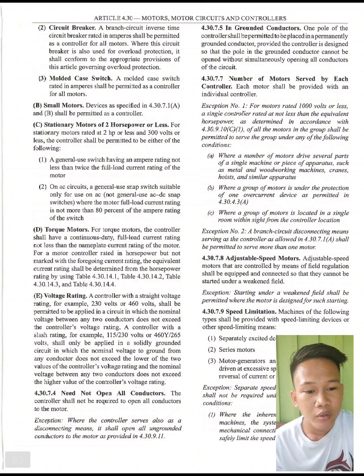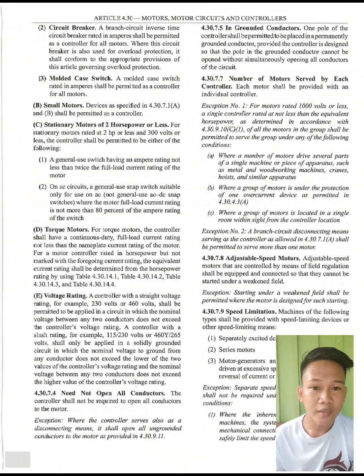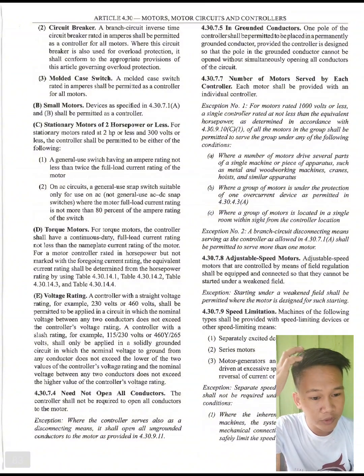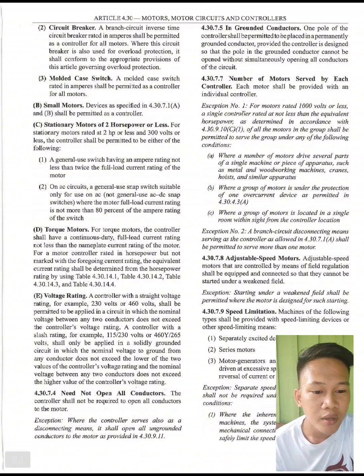Second, where a group of motors is under the protection of one overcurrent device as permitted in 4.30.4.3a. Third, where a group of motors is located in a single room within sight from the controller location. Exception number 2. A branch circuit disconnecting means serving as the controller as allowed in 4.30.7.1a shall be permitted to serve more than one motor.